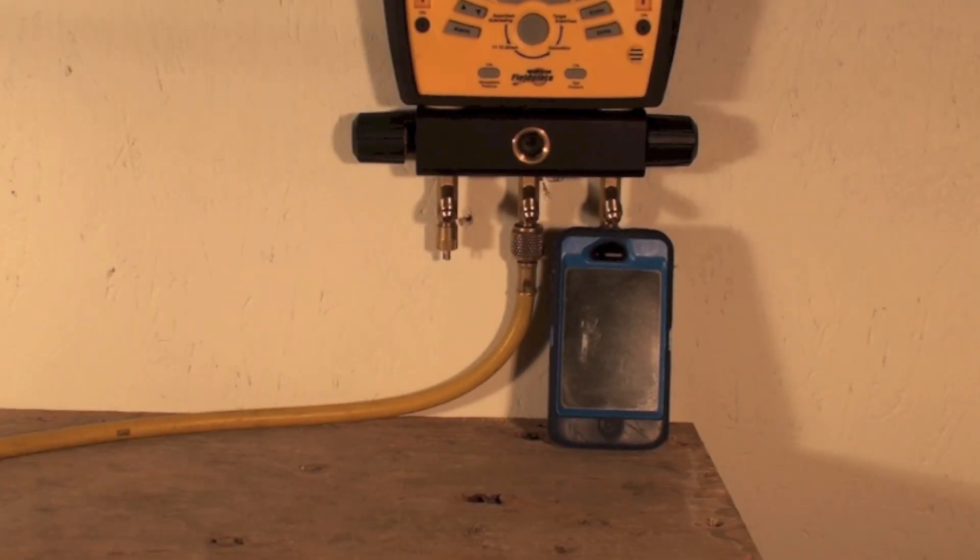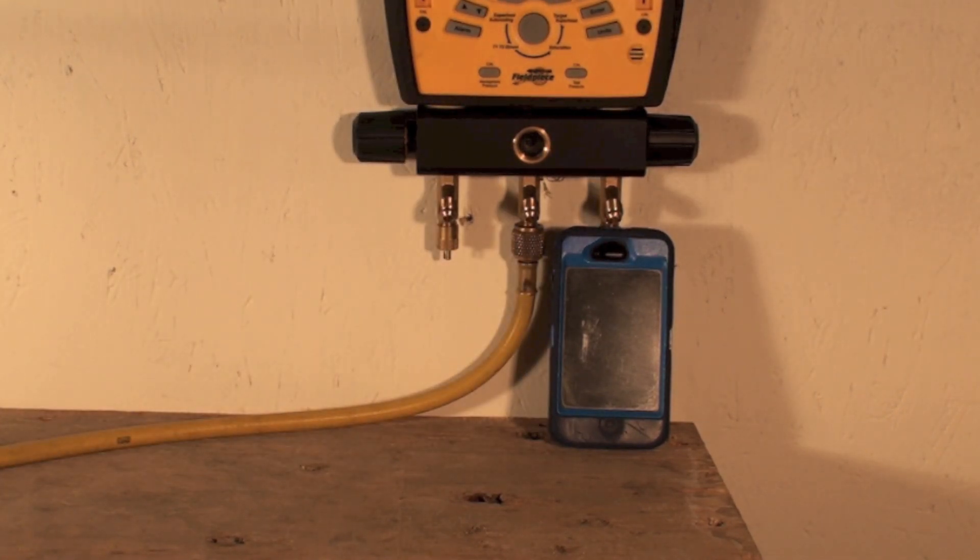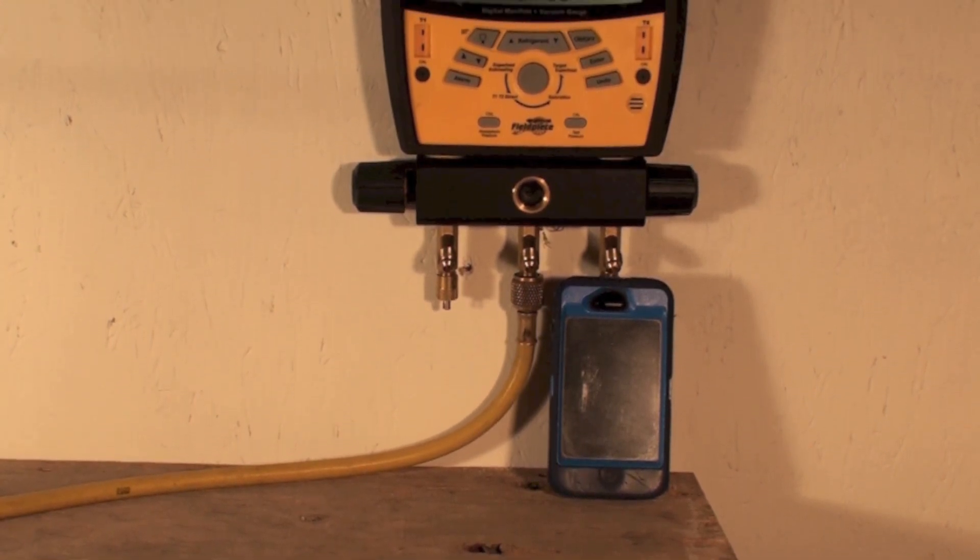Okay, here I've set this same thing up with a flexible hose. Now I've made a couple of changes. This is an almost brand new hose, but not quite. It has new gaskets in it, but there's no valves in it. The other one I used had a valve in it, that could make the evacuation longer. So we're comparing it to the hard pipe in the amount of time it takes to pull down a vacuum. So I'm going to go ahead and get this thing started.